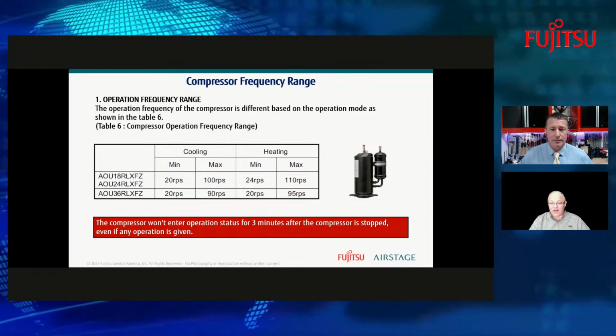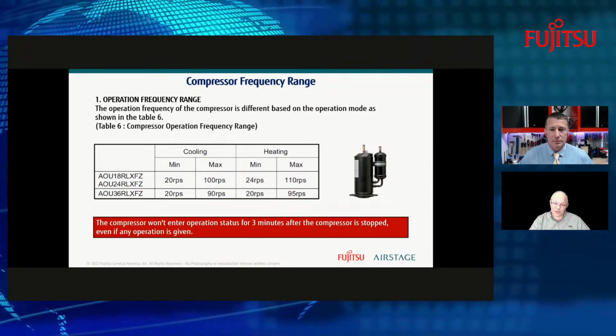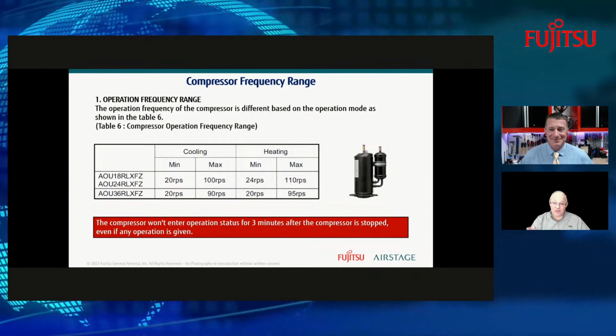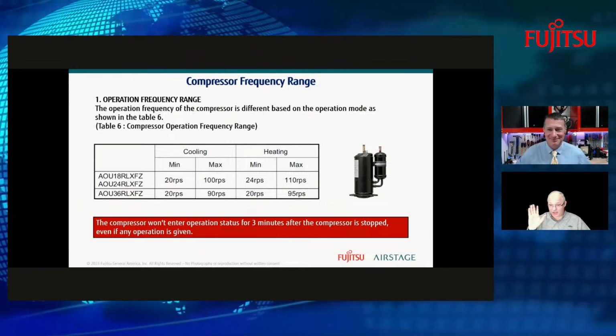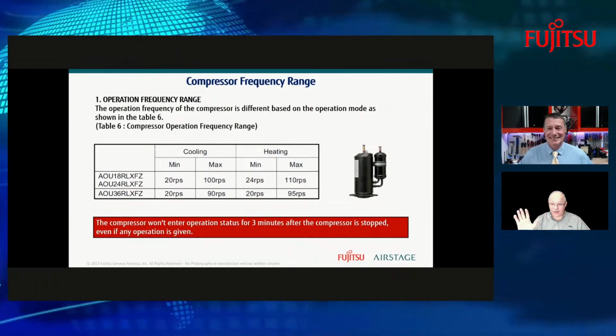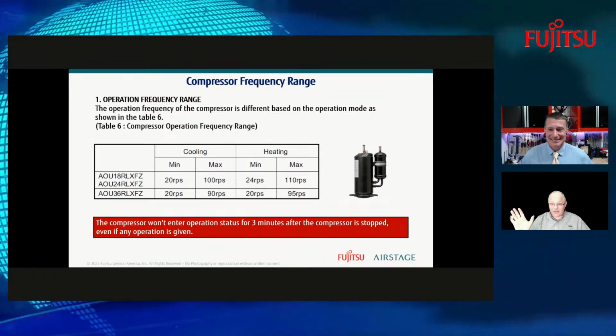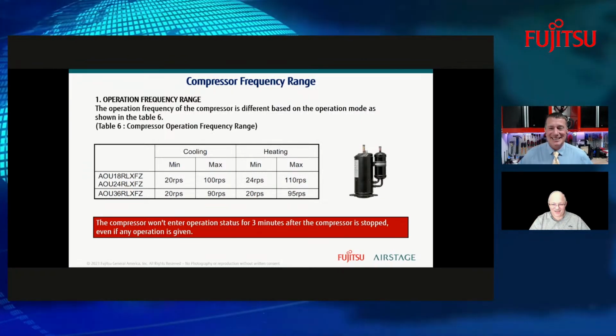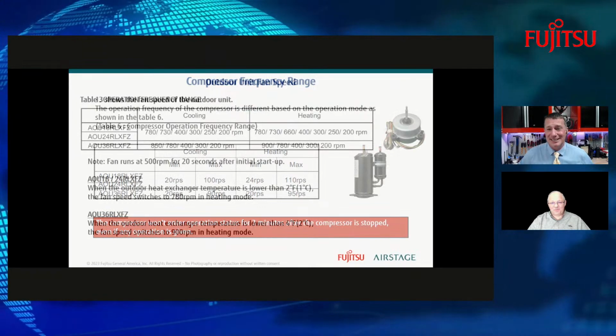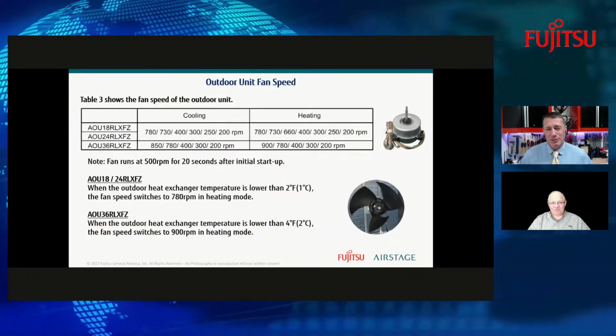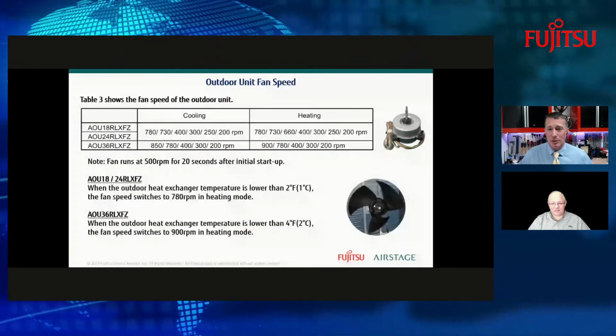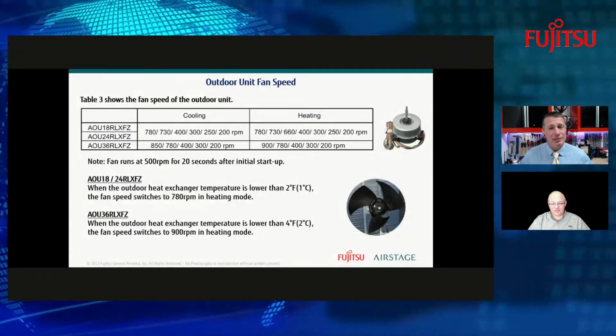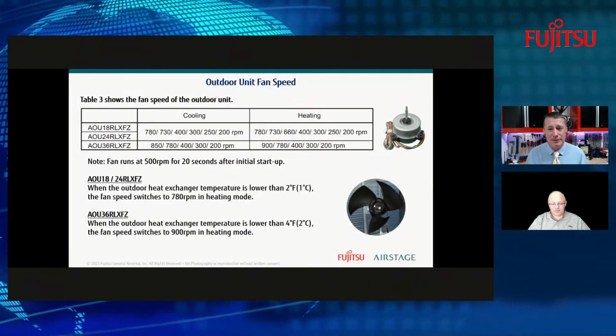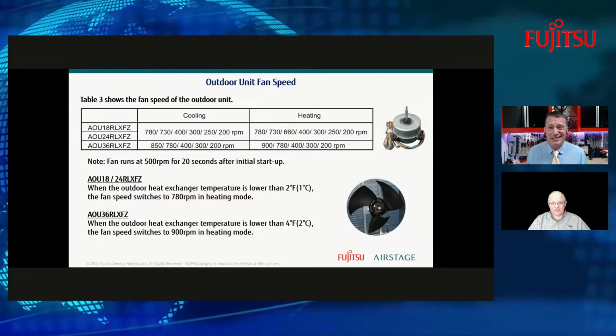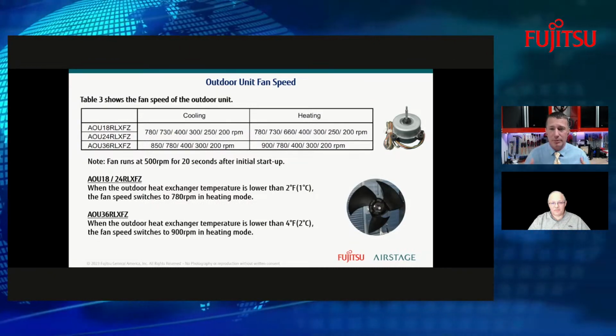Yeah, absolutely. So that's different when you compare that to a traditional system that is just single RPM speed. It doesn't know what's going on. It's kind of like it hasn't grown up yet. Yeah, exactly. A lot of people don't even realize that most of our traditional two-stage systems don't change RPMs. They just bypass refrigerant to change the load. So the motor of the compressor is just running at a steady state. It's never doing variable capacity.